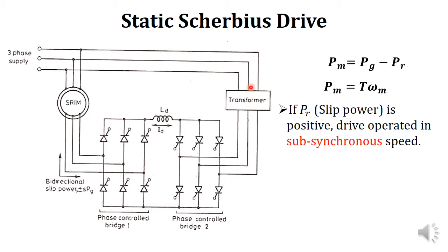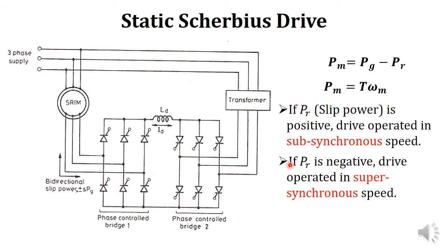Power flow from motor to supply mains is considered positive, and from supply mains to motor is considered negative. So if the slip power is negative, the drive operates in super-synchronous mode, because if Pr is negative then Pg − Pr increases, so Pm increases, speed increases, and it operates in super-synchronous speed.